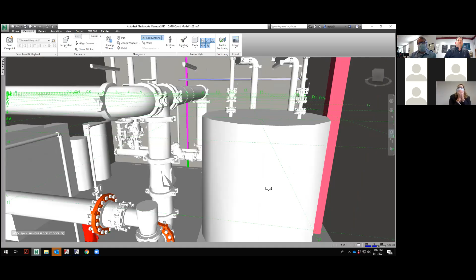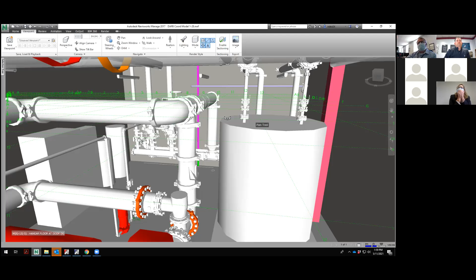This is what they call a foam tank, where all the foam solution sits. The water goes through these fire pumps, back down through the risers where they shut off the water, and then through the risers. Water comes up through these pipes out the top of the risers, and the foam solution comes through these little lines and gets mixed in with the water at what they call a proportioner. Then that foam-water mix goes out to those generators I showed you.